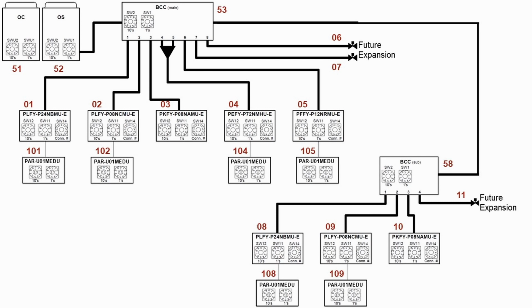Since ME controllers are controlled by address, they look up the daisy chain and they will control every indoor unit up to a maximum of 16 until it sees another ME controller, and then it will stop. In this case, address 102 is controlling indoor unit number 2 and 3, and it will stop when it gets to address 4 because it sees that 104 is connected. And then, of course, 105 is controlling unit number 5. 108 is controlling indoor unit number 8, and 109 is controlling indoor units 9 and 10.